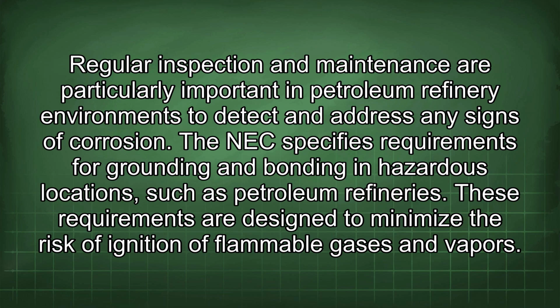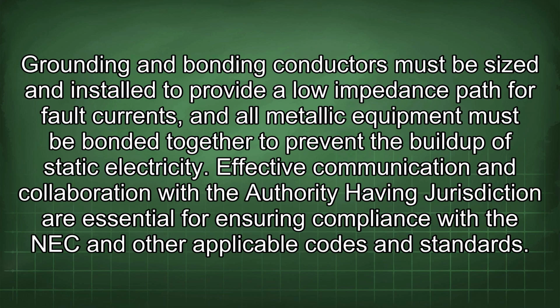The NEC specifies requirements for grounding and bonding in hazardous locations, such as petroleum refineries. These requirements are designed to minimize the risk of ignition of flammable gases and vapors. Grounding and bonding conductors must be sized and installed to provide a low impedance path for fault currents, and all metallic equipment must be bonded together to prevent the buildup of static electricity.